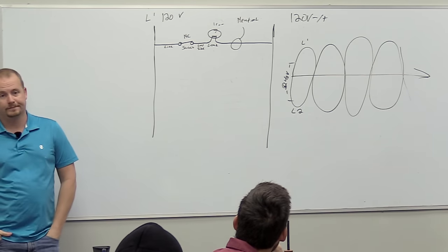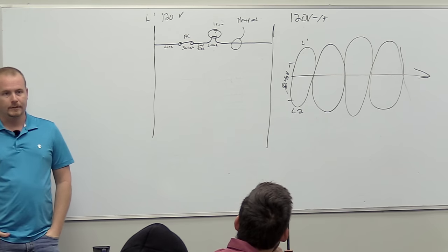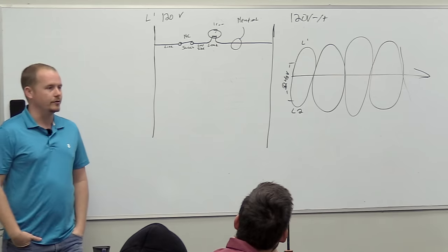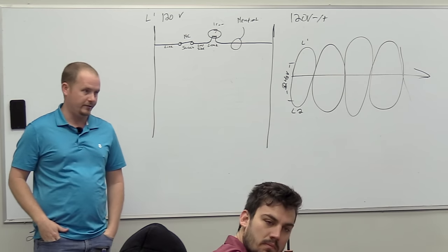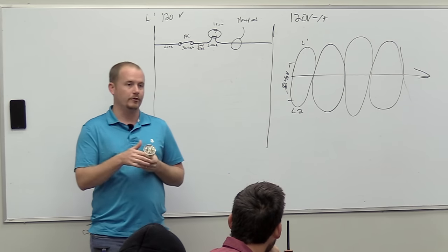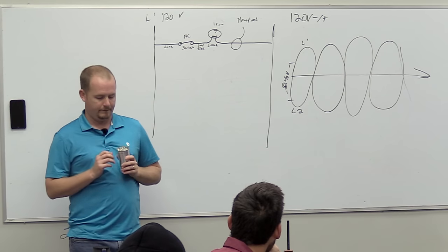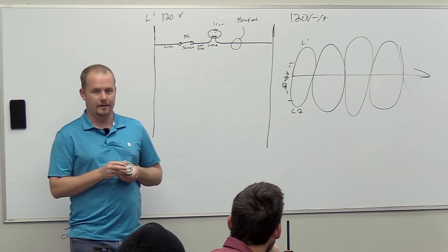Yeah, but common usually does too. Common is a more generic term. So common, you'll see common used in all sorts different applications. Perfect example is this run capacitor here. Did anyone know the three terminals on this run capacitor? What are they? It's common, herm, and fan. Yep. Common, herm, and fan. Yes.